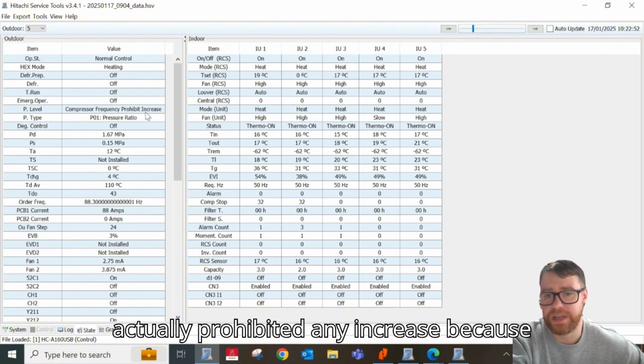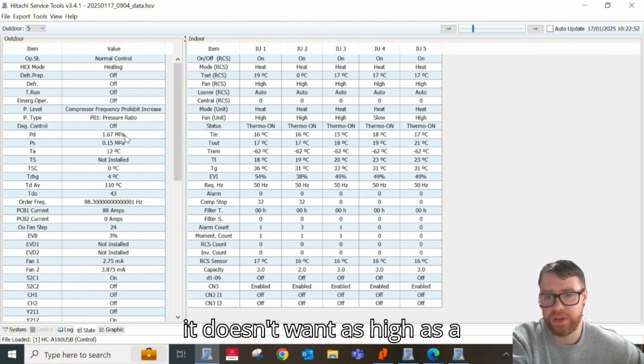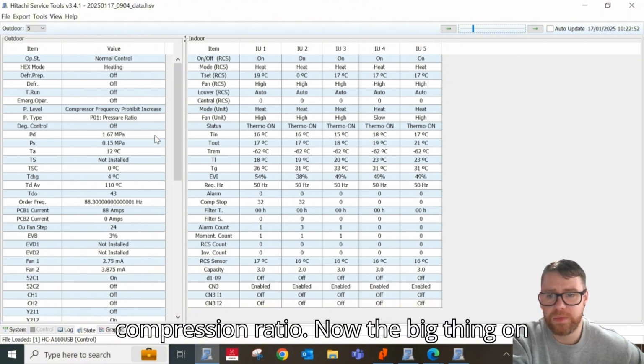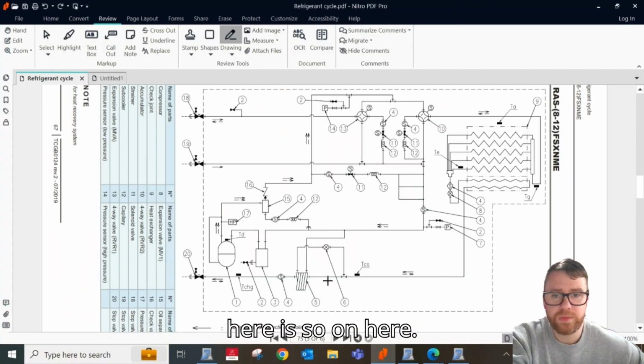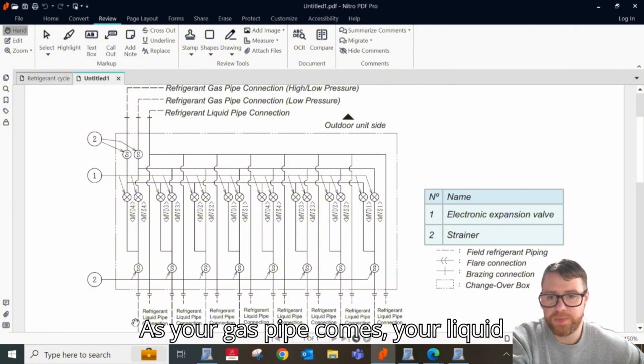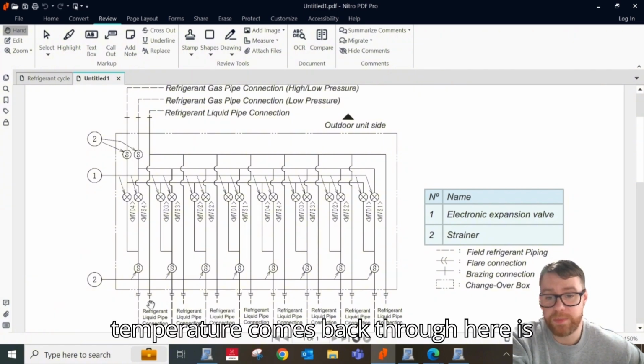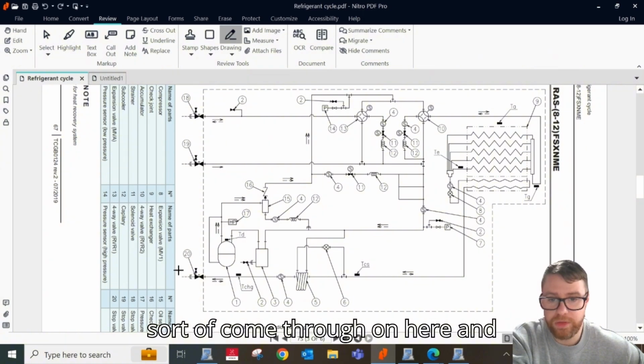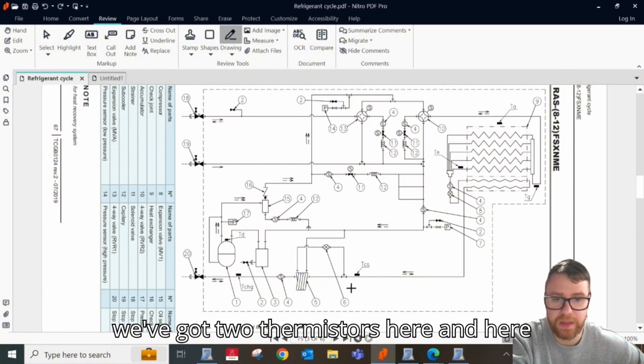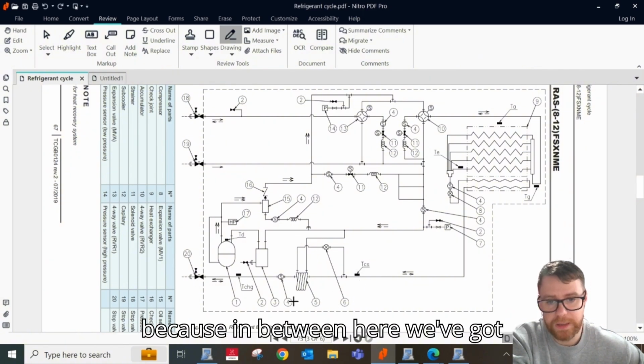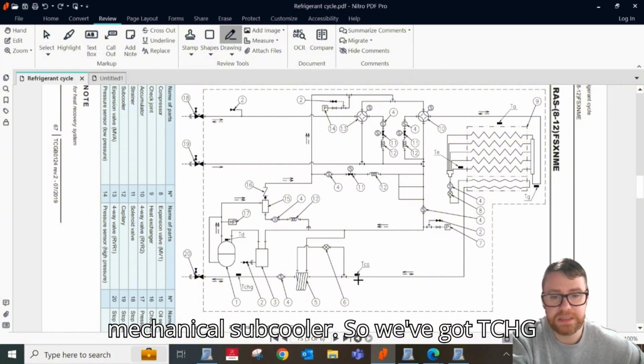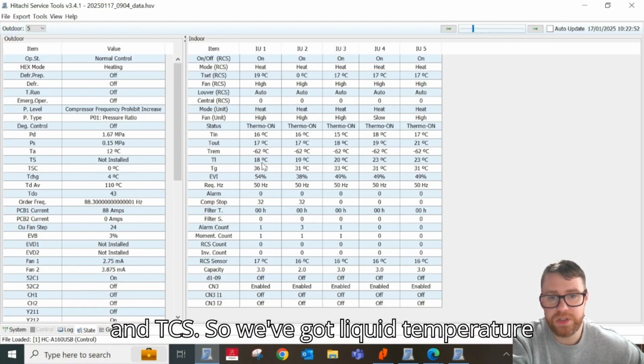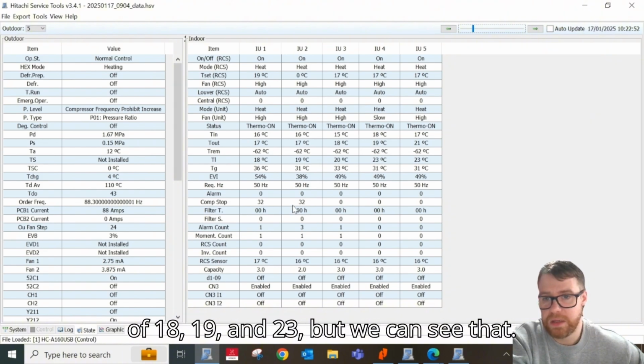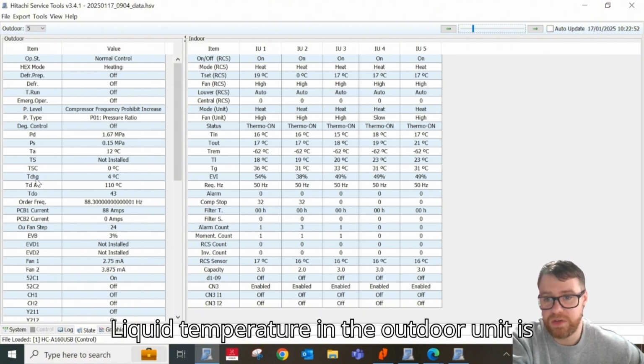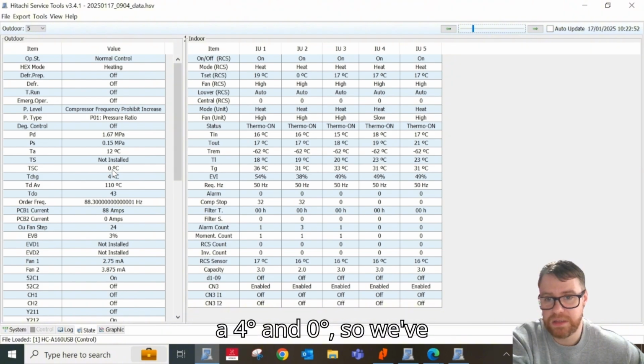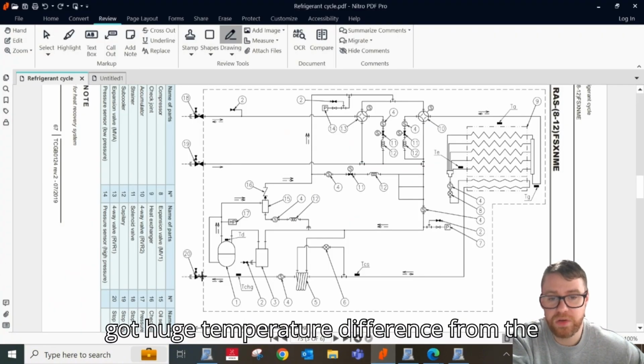So it's actually prohibiting any increase because it doesn't want as high a compression ratio. Now, the big thing on here is, as your gas pipe comes, your liquid temperature comes back through here. It's going to come through on here, then we've got two thermistors here and here, because in between here we've got a mechanical subcooler. So we've got TCHG and TCS. So we've got a liquid temperature of 18, 19, 20, 23, but we can see that our liquid temperature in the units is at 4 degrees and 0 degrees. So we've got a huge temperature difference from the indoor to here.